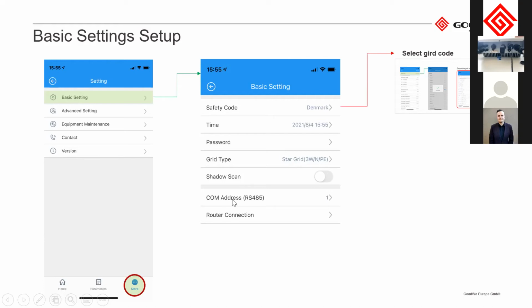The COM address is for if you connect multiple devices to a data logger, then you can choose exactly which COM address you will use for this inverter. The router connection is for the internet connection, and this is where you set up the internet setting of the inverter. So basically you click there and then you search for the correct internet that you have in the house or in the facility, and then you enter the password and that will be set.